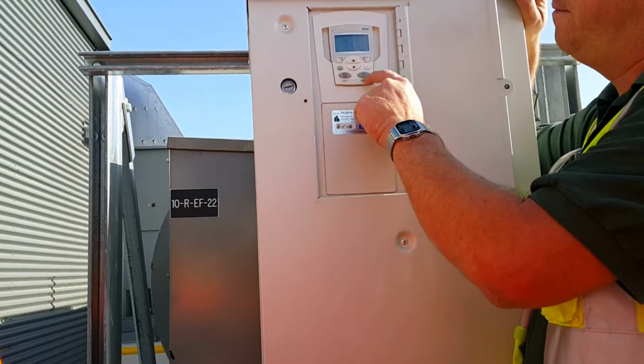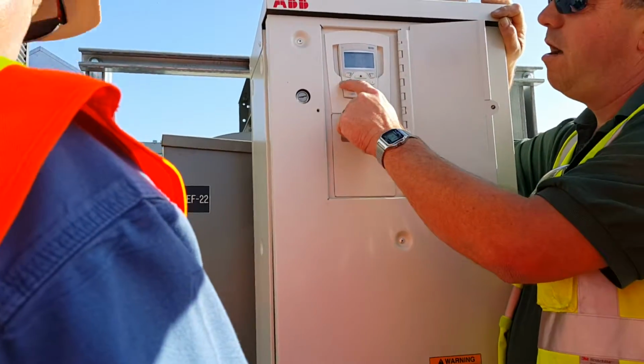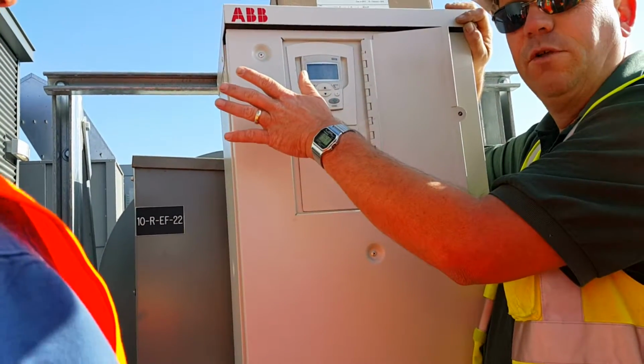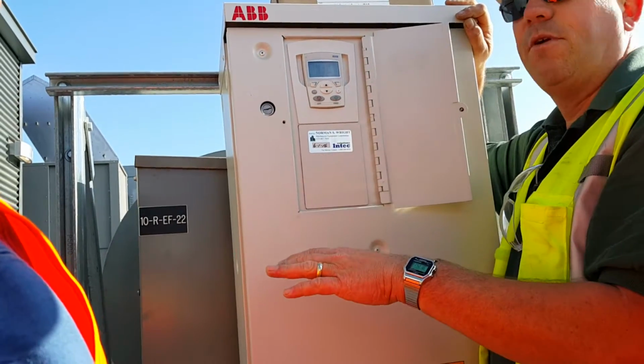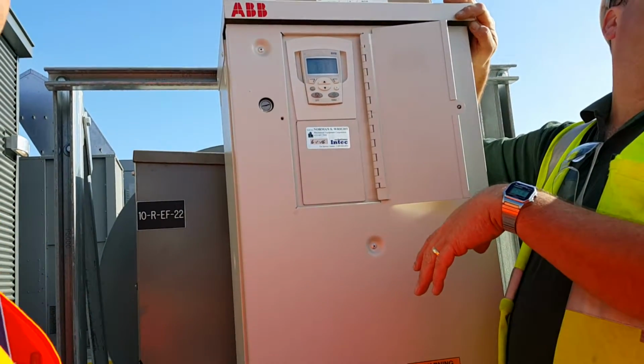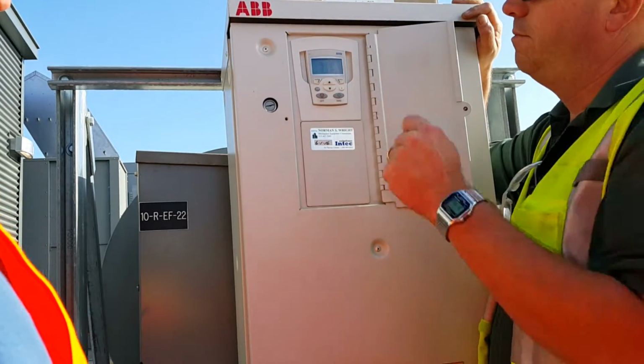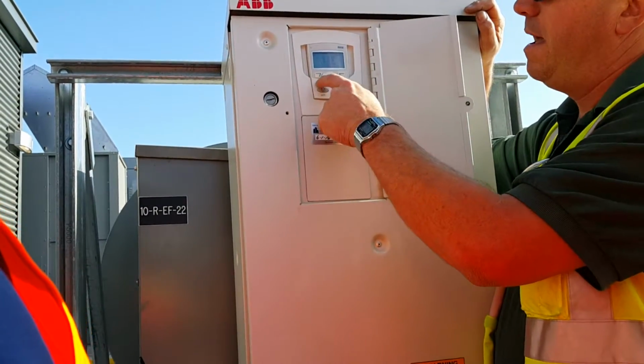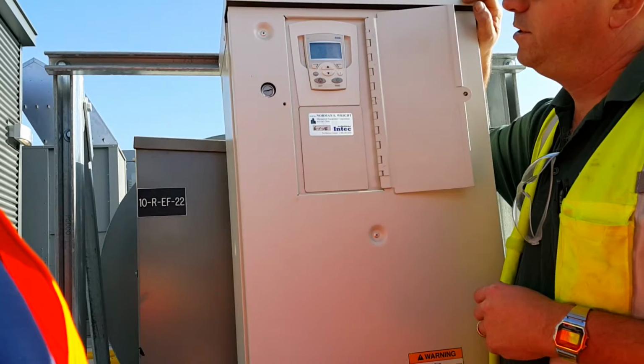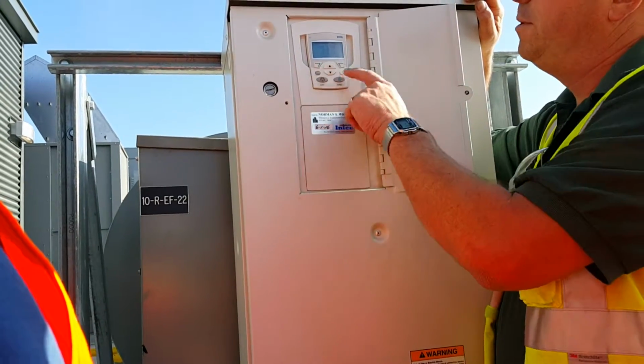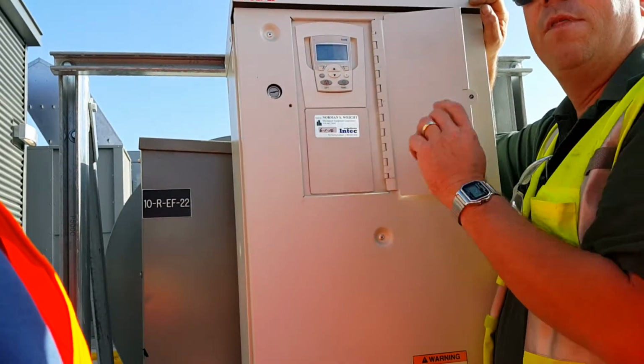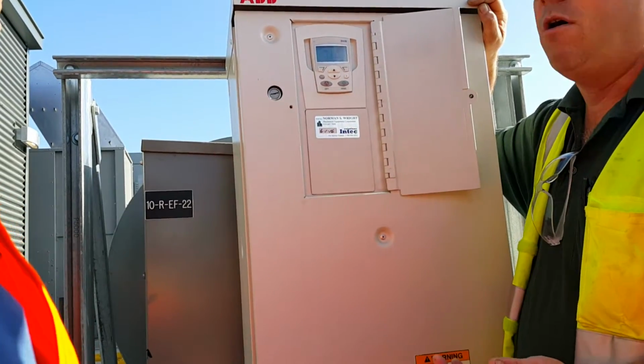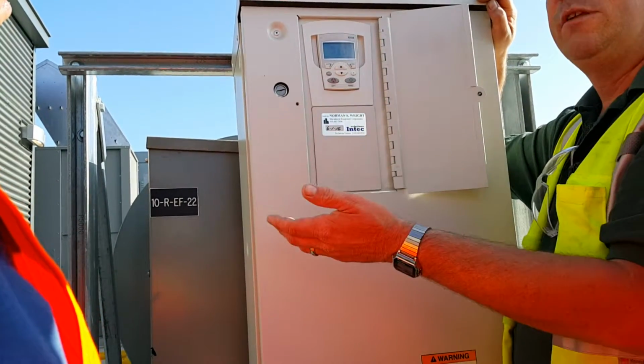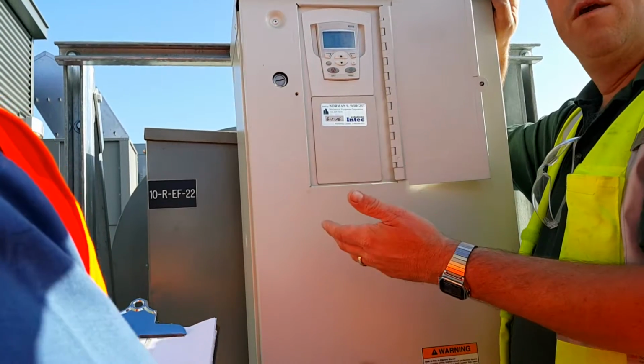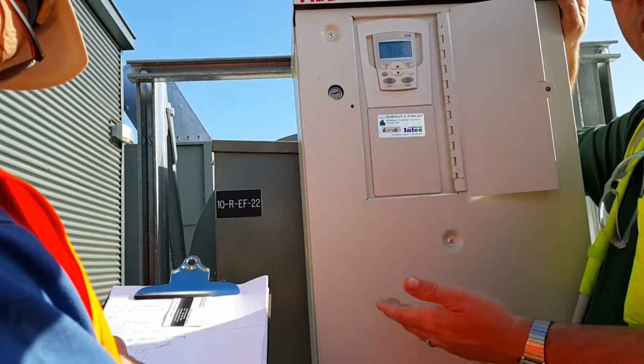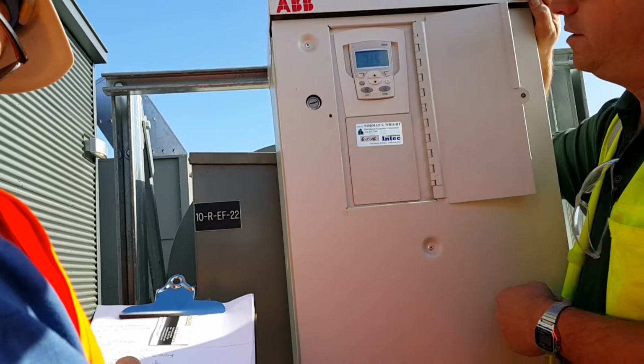You have your hand, off and auto buttons. Auto, your BMS is in control of the drive. Off, it'll stop the drive. Is this one all right to stop and play with? Okay, cool. So, boom, stopped, right? You put it back in auto, and it restarts. You don't have to wait. You can also go between auto and hand and auto without going through the off position. You can't do anything wrong. So what it'll do is just start us out in hand right where we are in auto if we are running. If we're not running, of course, it'll start the drive.